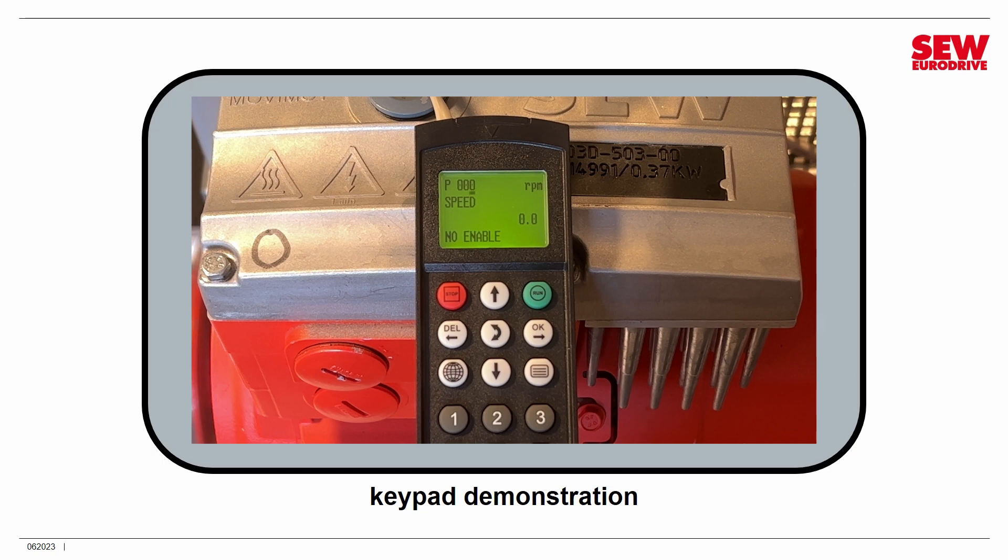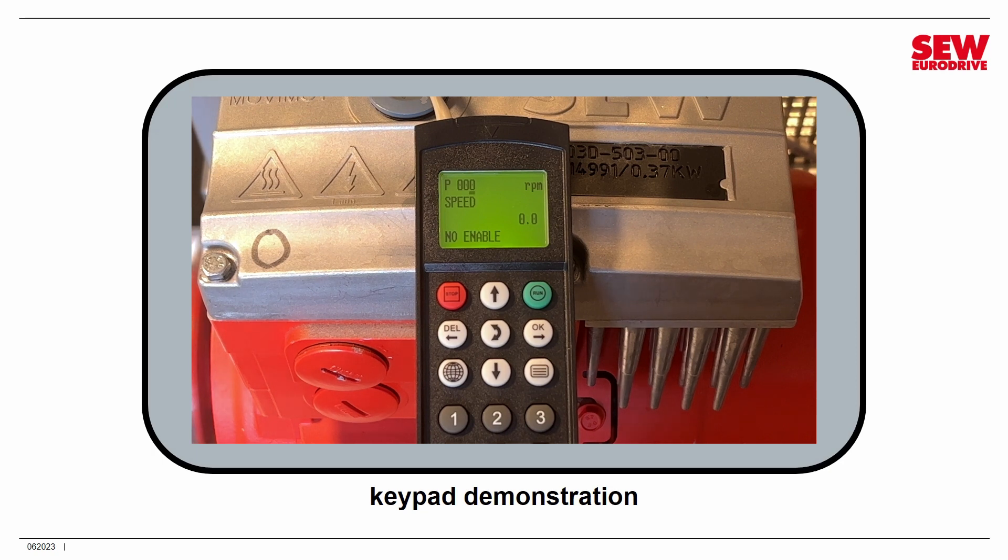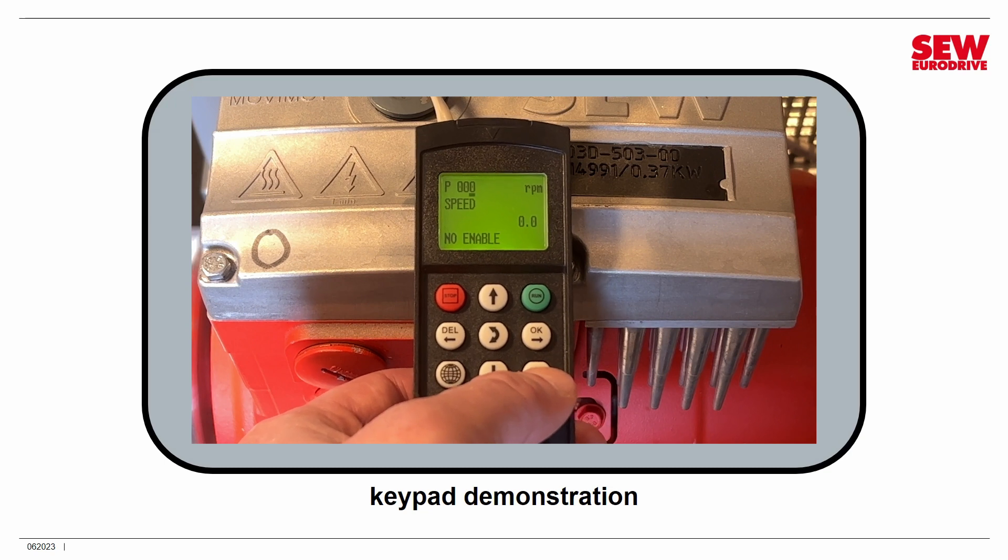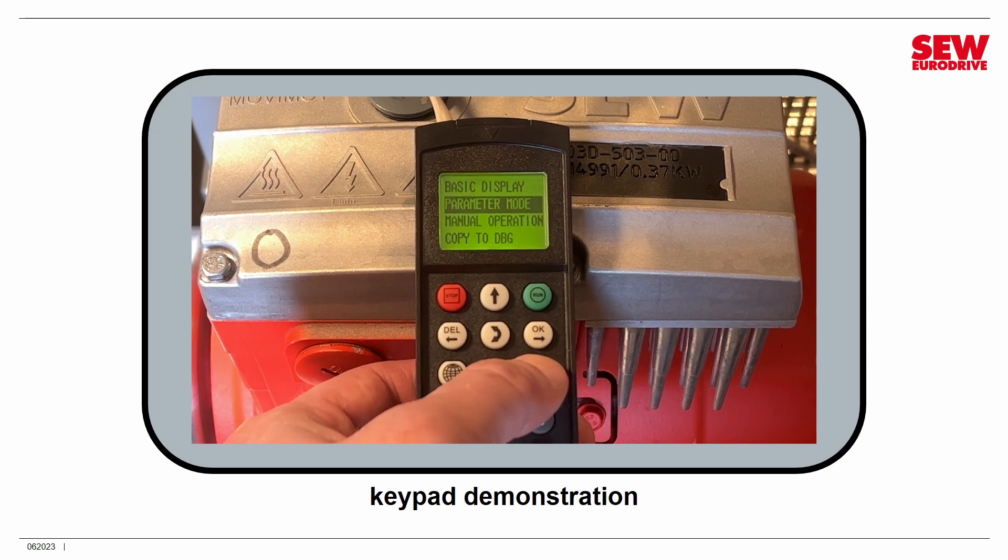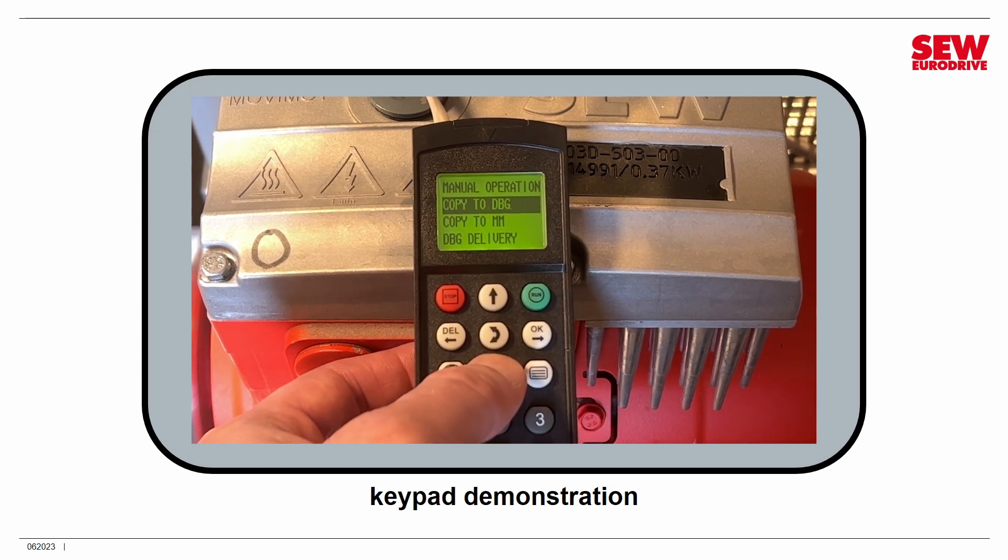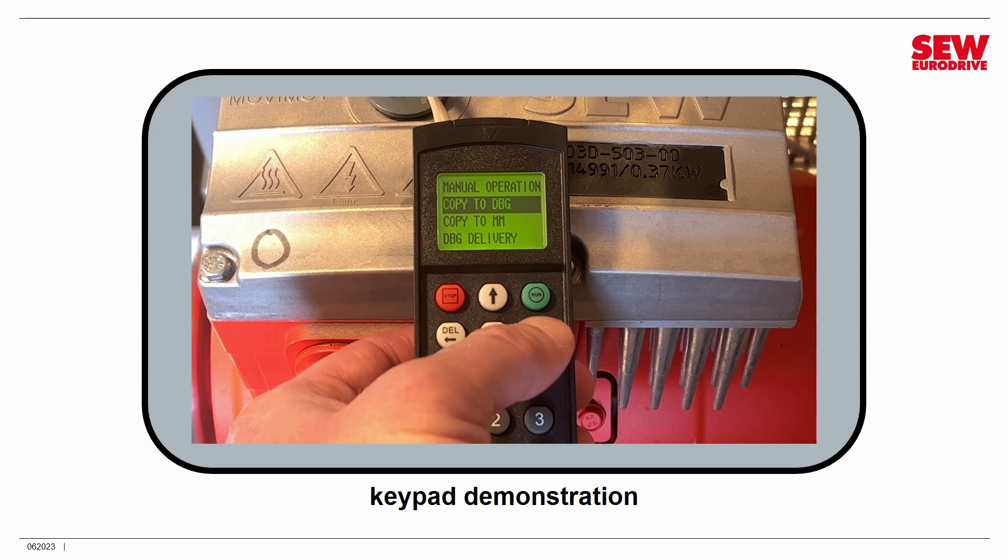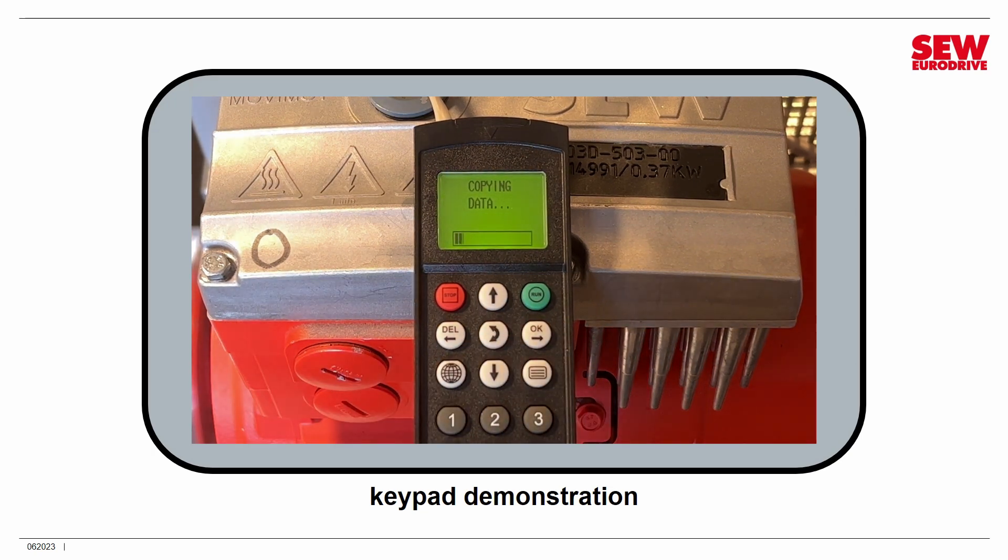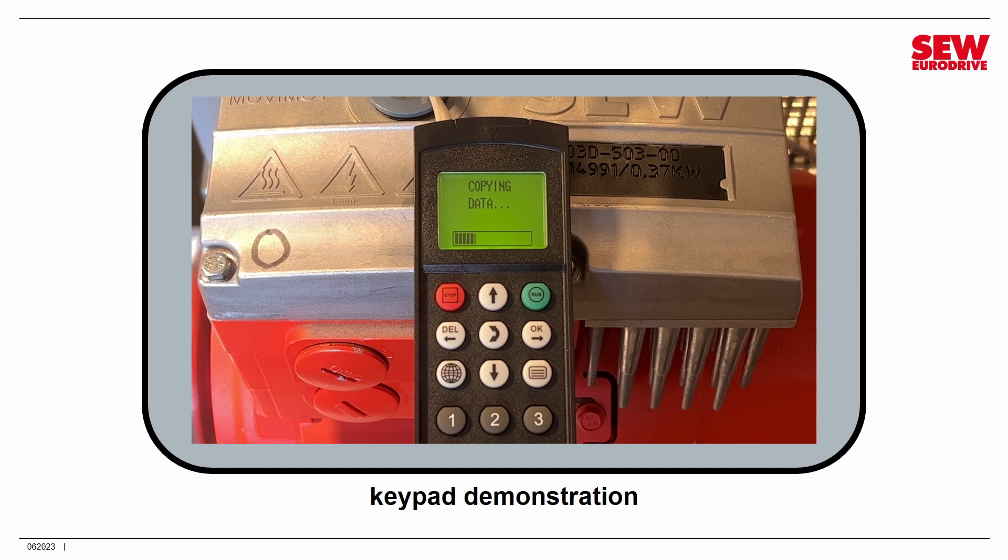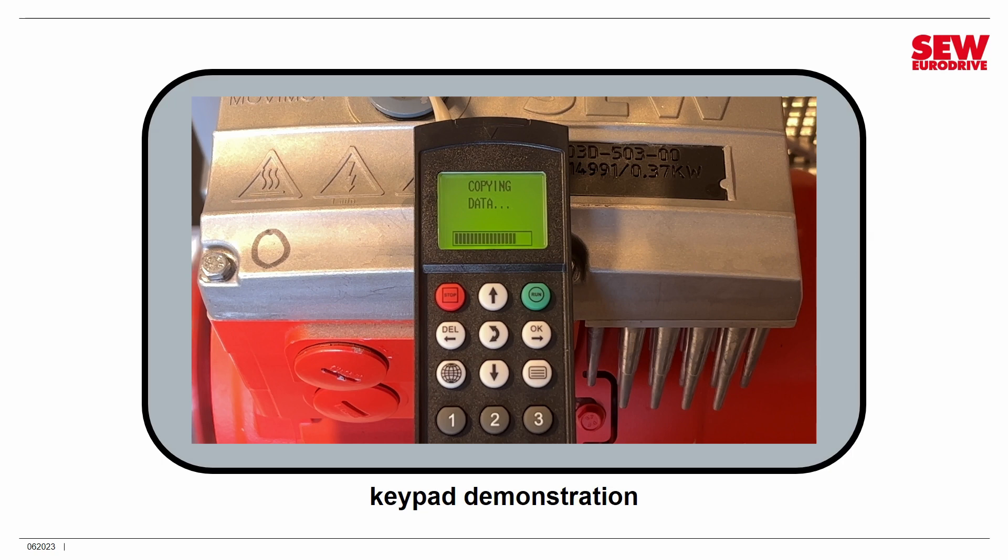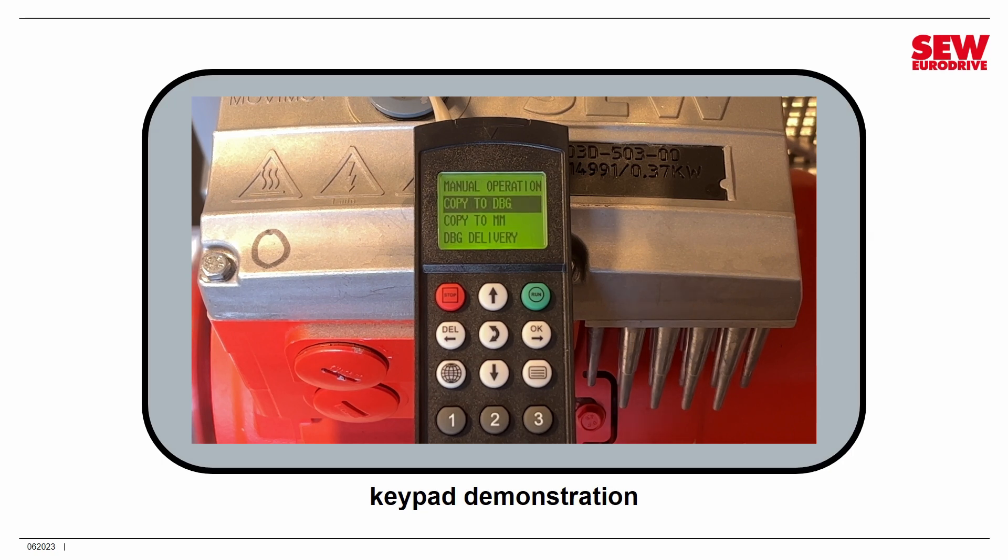Now let's look at how we do a backup. The keypad can hold a single backup image of the parameter set. To access the backup function, we would again hit the menu button. And then we would navigate down to copy to DBG and press OK, and notice as soon as you do it, the backup begins immediately. There's no warning, and there's only one backup that can fit in memory, so if there's one in there, it's being overwritten right now. So always be careful with the keypad. You don't get a lot of chances to back out of things. It takes about 15 seconds to make the backup, and there it goes.